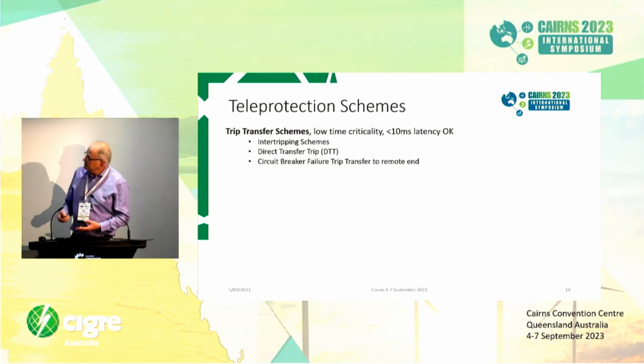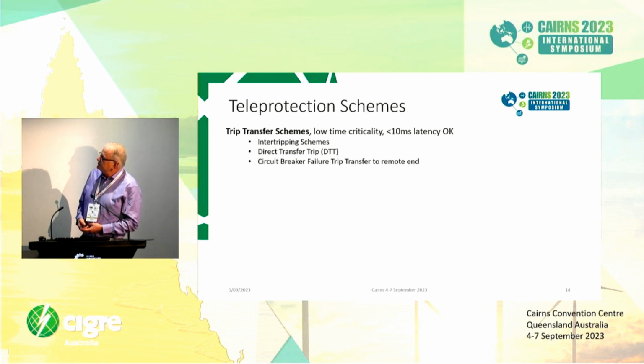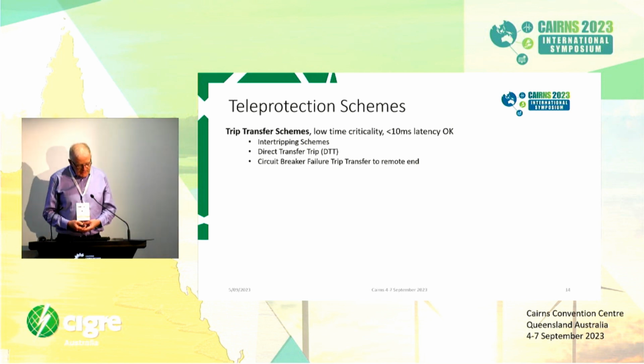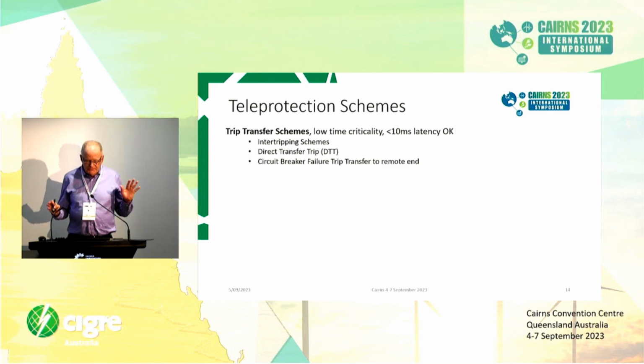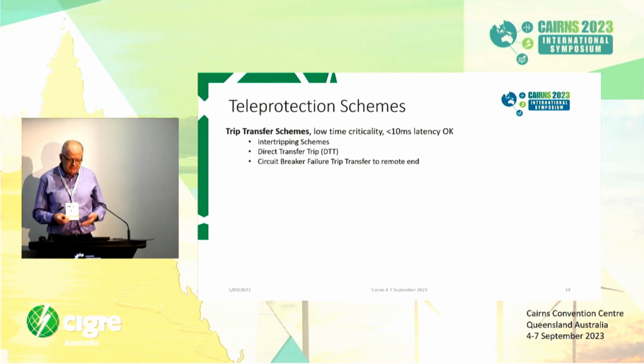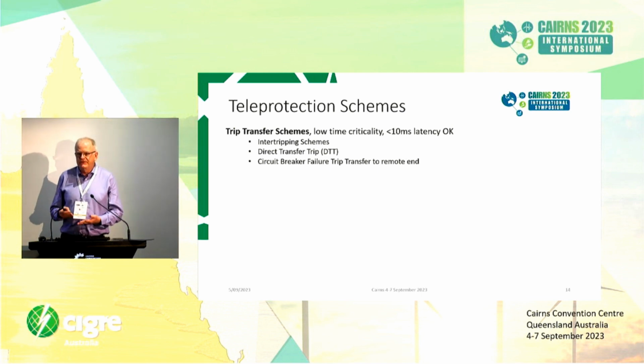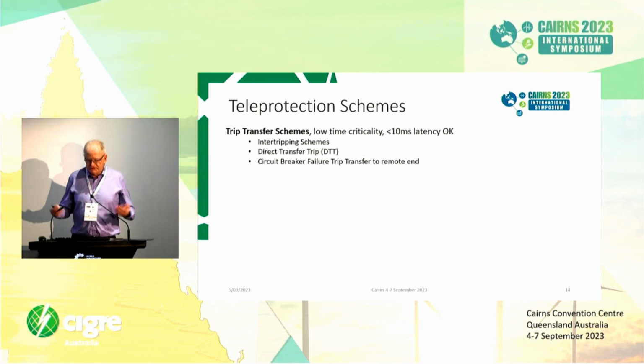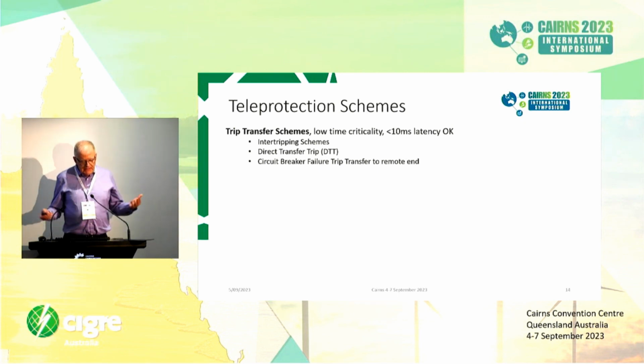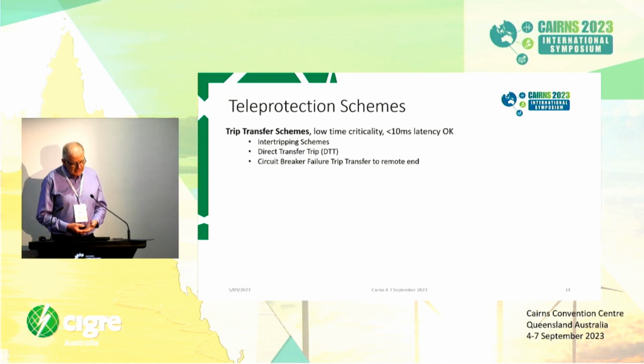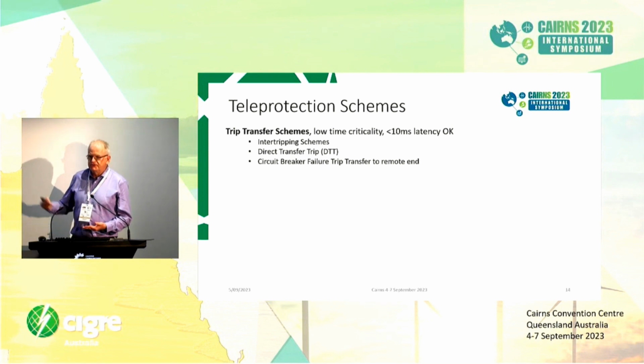So a bit about some protection schemes that use communications enablement. So we've got trip transfer schemes. Typically these are low time criticality, up to 10 milliseconds of latency is okay. We just need to guarantee that the trips are going to arrive at the remote end within a reasonable time frame to meet the protection fault clearance times. And types of schemes there are basic inter-tripping schemes, direct transfer trip, or circuit breaker failure trip transfers to the remote end of a line.